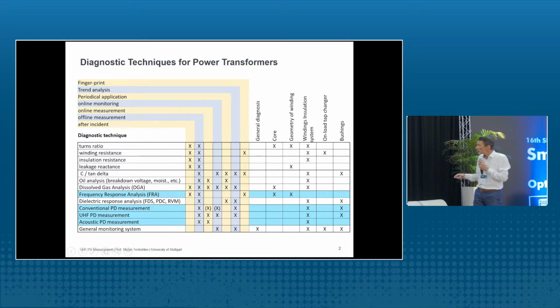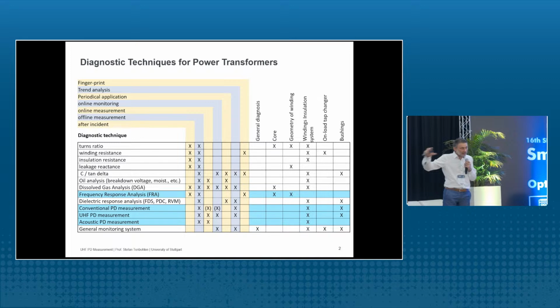The other measurements are online measurements. Online means that the transformer is connected to the network. So let's say you have the normal operating condition of the transformer, and you can then go with your measurement technique to the transformer and measure, let's say, for 1 day. Or also you can keep the measuring technology at the transformer and you monitor the condition over a long period. In this case, it is called online monitoring. We have here a lot of diagnostic techniques. I will talk today about frequency response analysis and about partial discharge measurement.